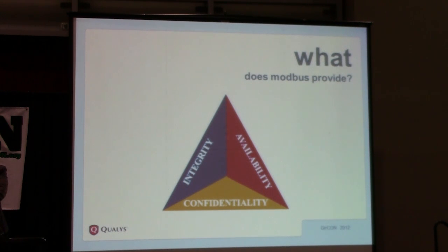And it was not really designed with security in mind. So we created a signature saying that if we find Modbus running in your environment, or your HMI and your field equipment communicate using Modbus, then you have a potential vulnerability, because the protocol itself doesn't support all these things. So you have to secure your environment using other measures around that protocol, and we'll look at how to do that.